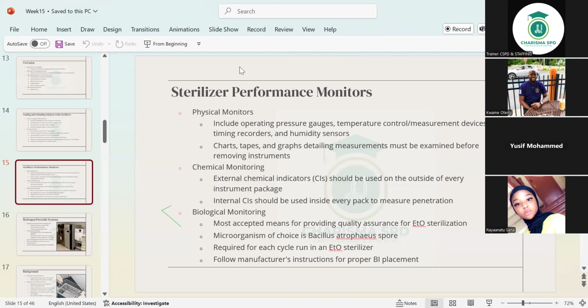And after the biological comes out, we have to incubate it to make sure the microorganisms in the biological indicator were all killed. That way we know the thing has come out sterile. Okay, so you see the kind of performance monitors. We have physical monitors, we have chemical monitors, and we have biological monitors. A lot of times it's going to be on the test. Kind of monitors that we have, sterilizer performance monitors. We have physical, we have chemical, and we have biological.